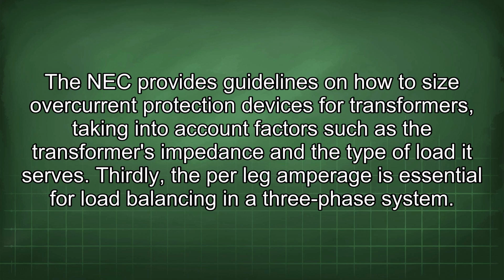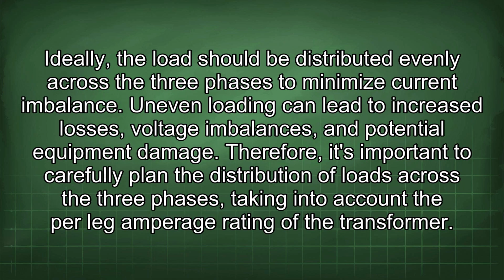Thirdly, the per leg amperage is essential for load balancing in a three-phase system. Ideally, the load should be distributed evenly across the three phases to minimize current imbalance. Uneven loading can lead to increased losses, voltage imbalances, and potential equipment damage. Therefore, it's important to carefully plan the distribution of loads across the three phases, taking into account the per leg amperage rating of the transformer.